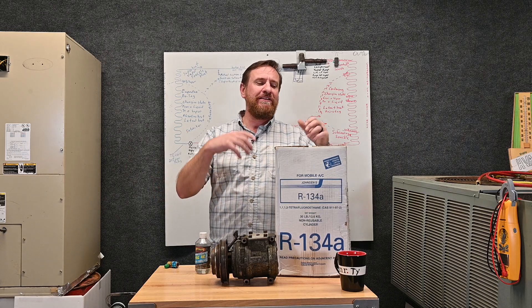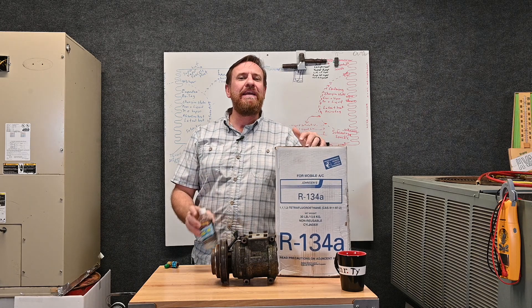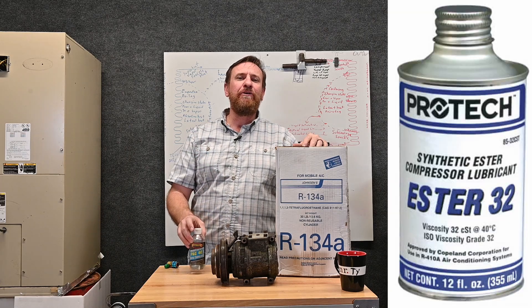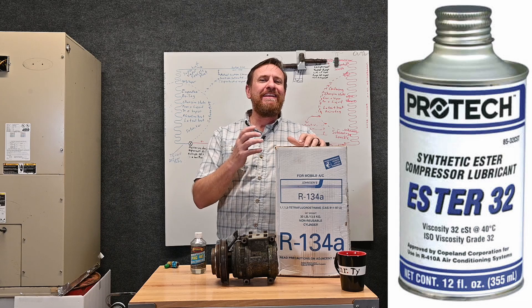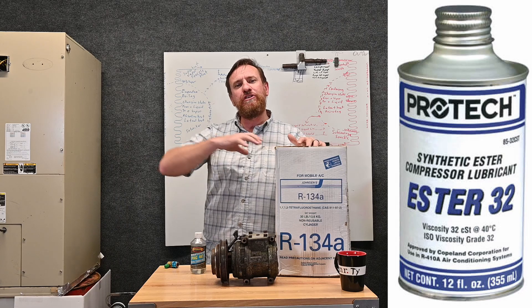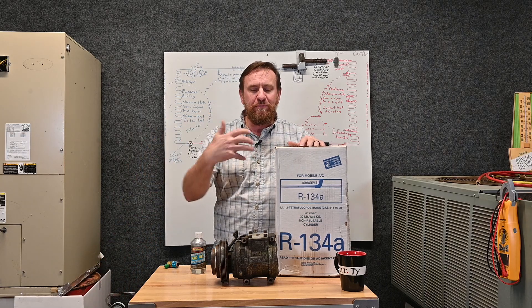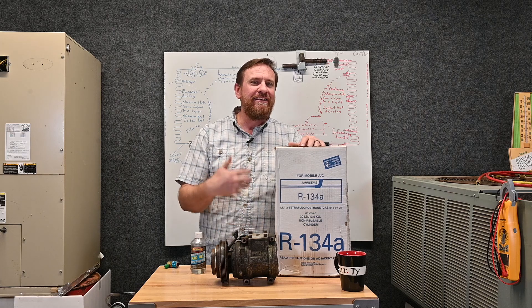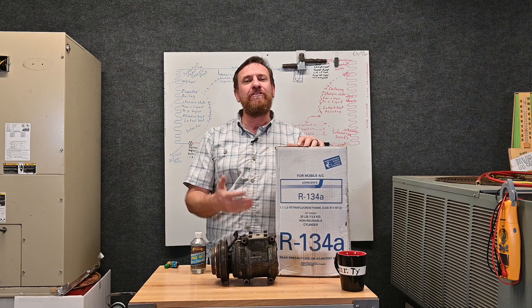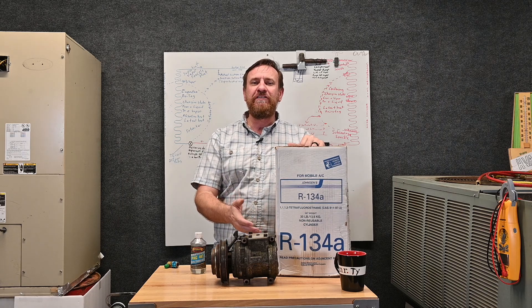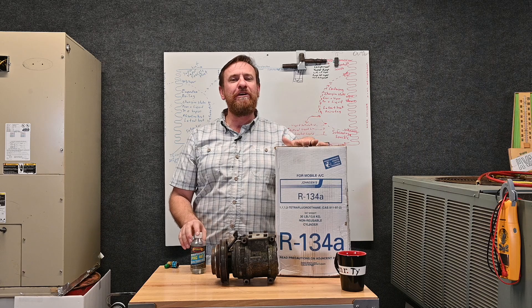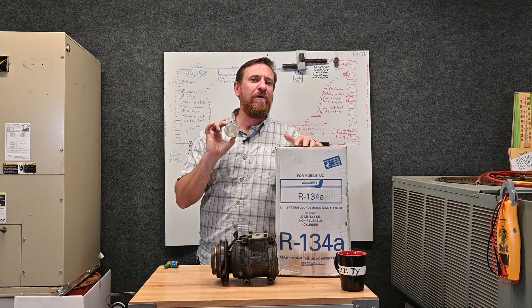The same thing applied to refrigeration systems — we had to get all the old oil out and put in the new oil. In refrigeration systems, it wasn't always PAG oil; a lot of times it was POE oil, polyester oil. The catch is that because there wasn't that chlorine molecule in the refrigerant, R134A would not carry the mineral oil through the system. Without proper oiling, the compressor would fail. A lot of people didn't follow that step — by switching over the refrigerant without switching over the oil, they had an oiling issue that would cause compressor failure. Making sure you had the correct refrigerant and the correct oil was very important.